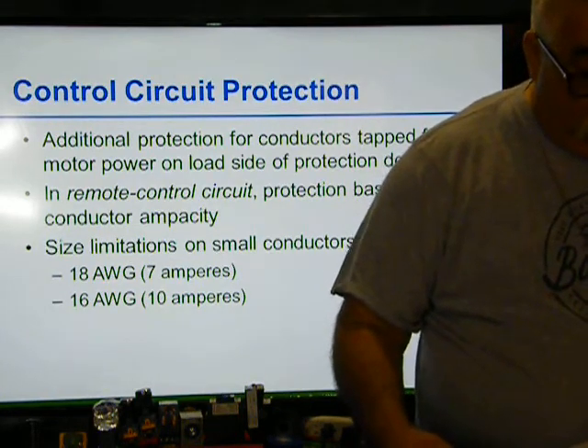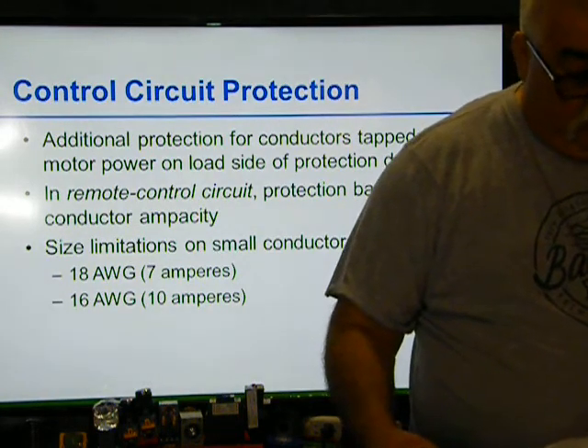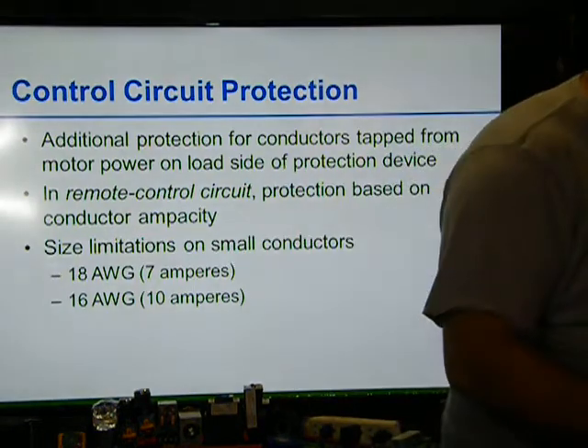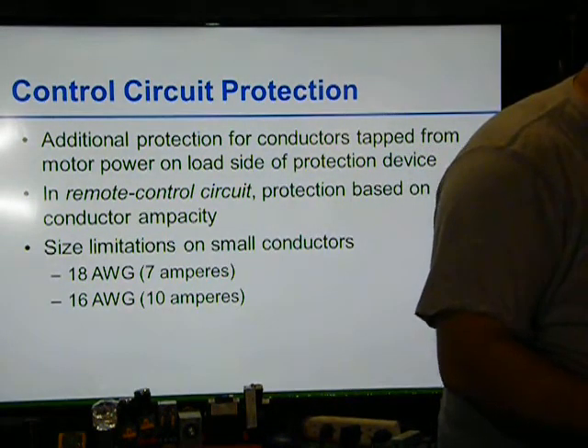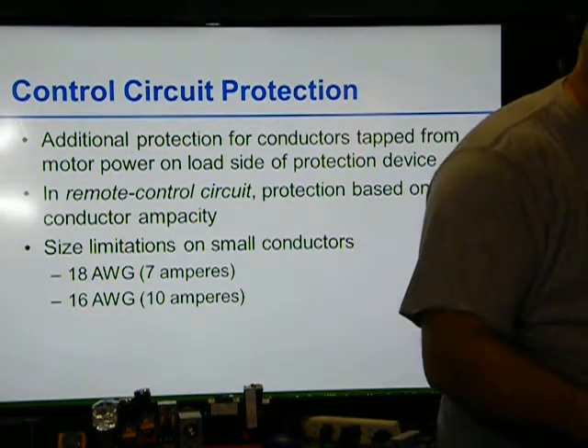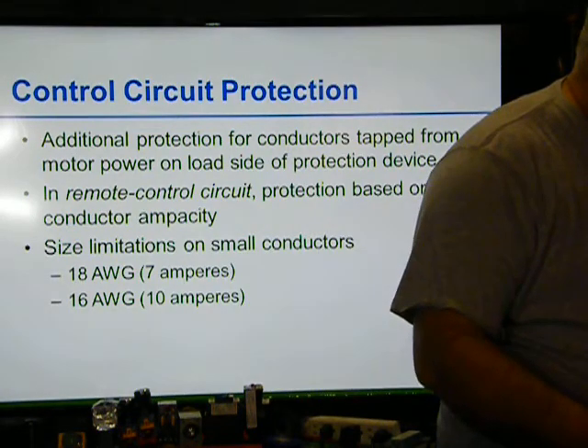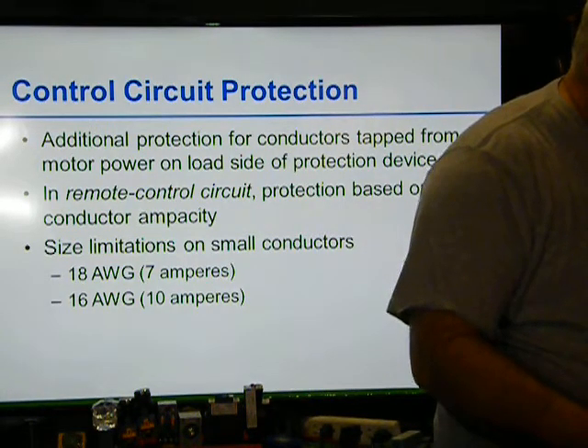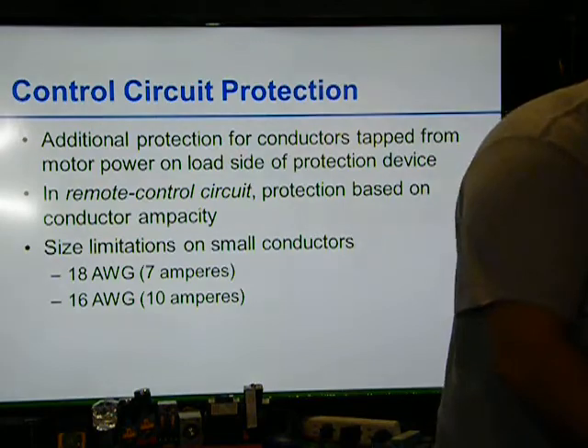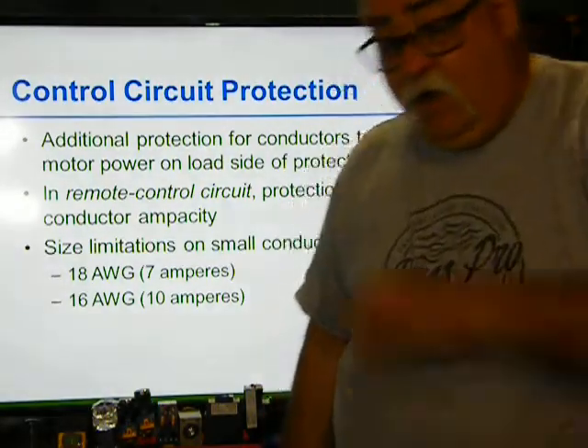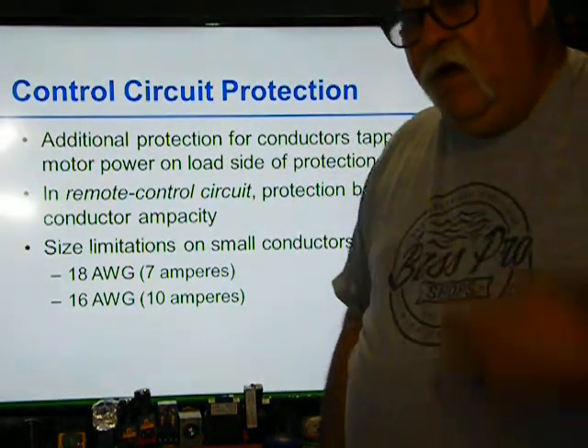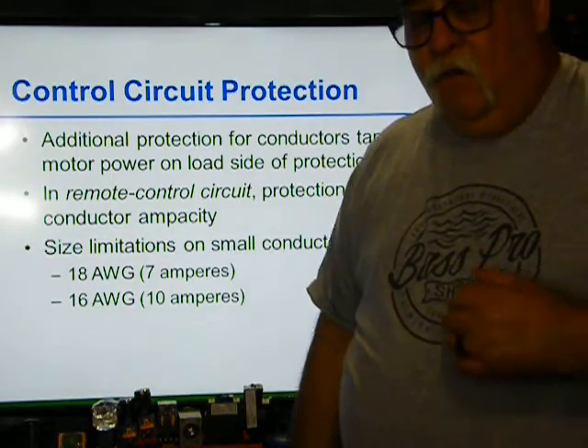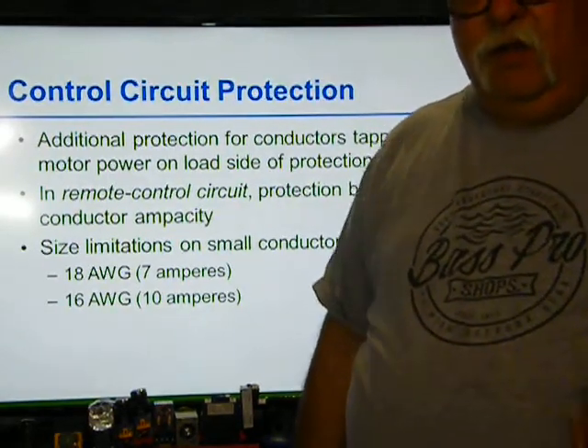In this case, the circuit is considered a remote control circuit, and the overcurrent protection is based on the conductor ampacity. Section 725.43 specifies that the conductor ampacity derate factors of Section 310 are not considered. So what does that mean? If I've got a wire going through a hot area, I don't have to derate the wire. Why? Because it's not going to be carrying a lot of current.